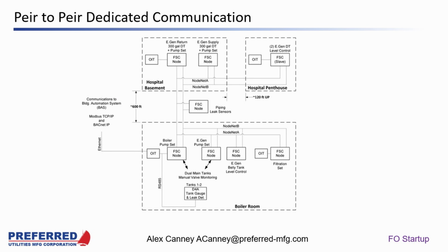It says, following up with the node A and B, so we had the question about the node net A and B with our FSC system. If the node A and node B run in the same conduit or run together, and a forklift breaks the line at the same time, because of that, do you run the node A and node B separately? It all depends on the requirements of the facility. I mean, if we're talking backup fuel for a boiler at a middle school, it's not really that big of a deal. But if we're talking a hospital or a data center, yeah, if they're looking at redundant fuel systems, N+1 on a lot of different things, we'll definitely consider running those separately. So, get a little bit of redundancy on the communication. And in fact, it's something that with a traditional system is nearly impossible to do.